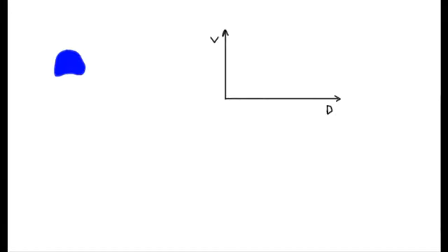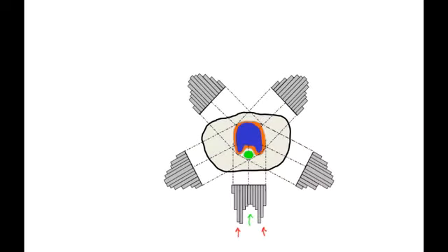So let me redraw this as a little cartoon so it's easier to talk about. Prostate PTV on the left, and let me draw the isodose line that you want and how it should conform around the PTV. So that's what I want to achieve, and if I were to achieve that, I would have a DVH that looks something like this. It comes over and it's nice and uniform, drops down as we've seen before, and then the leaf sequence corresponding to that, the fluence maps would look like this. So that's the ideal case.